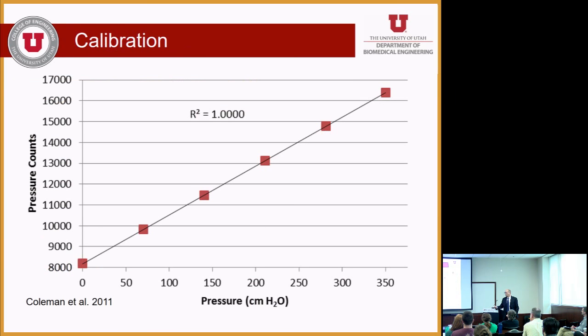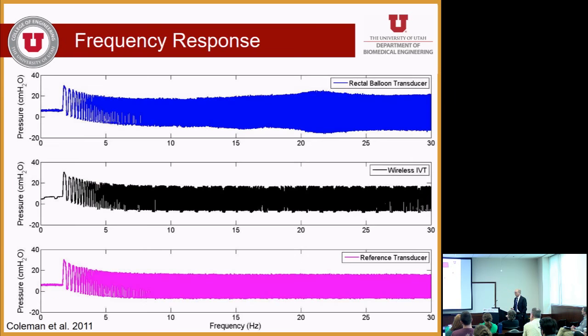So the devices work great, extremely linear. We compare them to the current standard. So the rectal balloon catheter, you can see on the top, rings a little bit at about 22 hertz because it's a fluid-filled system and we have dynamic response. And when you see people jump up and down, you actually get tremendous pressure excursions with a rectal balloon transducer. But with our wireless IVT, except for a little dropout because of sampling errors, we're pretty much rock solid with the reference transducer.